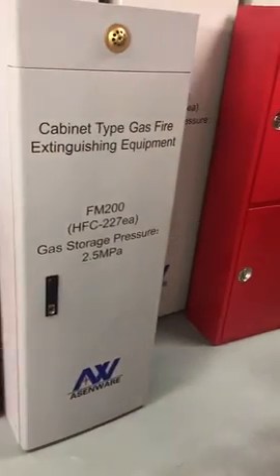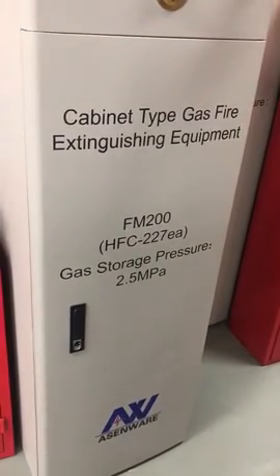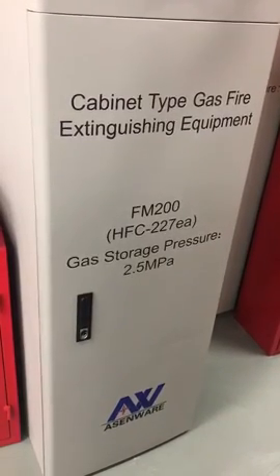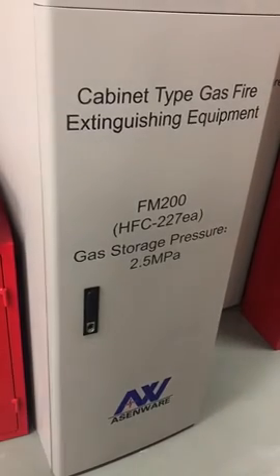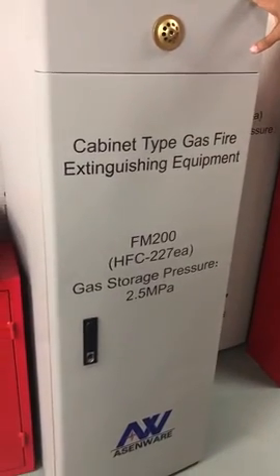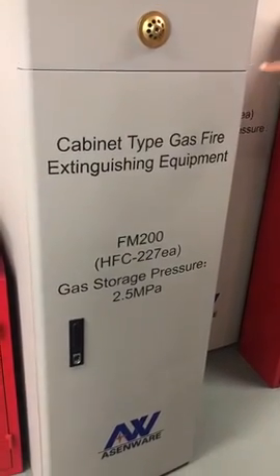This is the Asenware FM 200 cabinet system for extinguishing fire using gas. The gas name is FM 200, with the chemical name HFC 227. The stored pressure is 2.5 MPa. This system is utilized for small rooms, not very big areas. Big areas are preferred to use a piping system, but for a small area you can use this one.